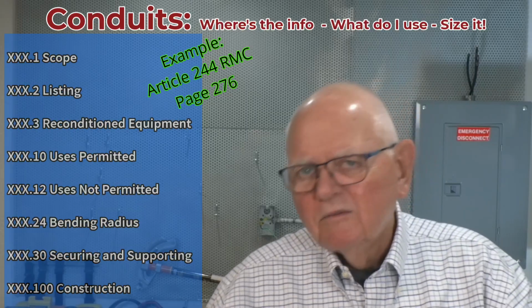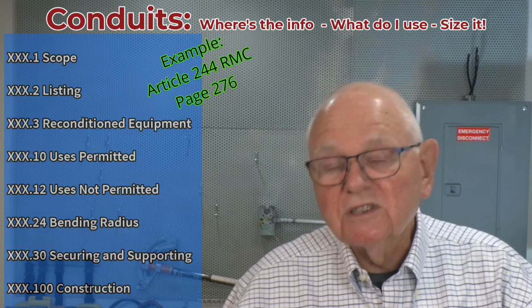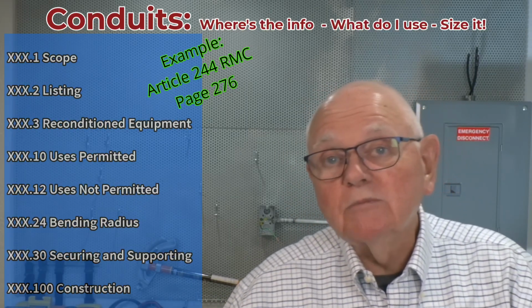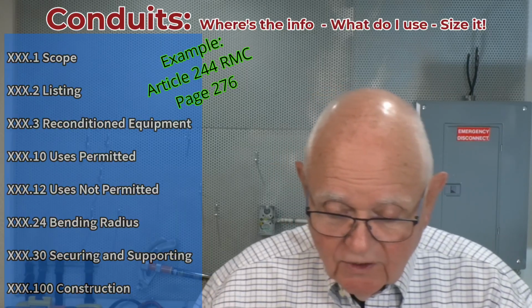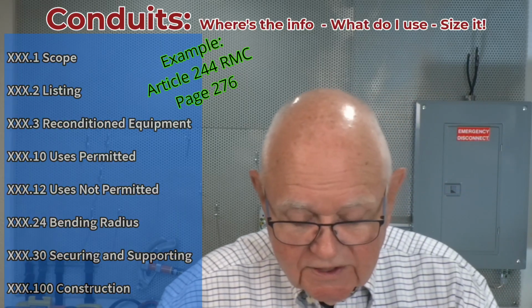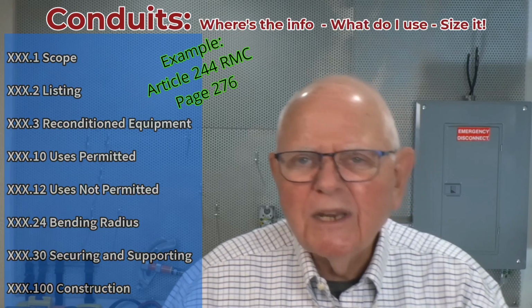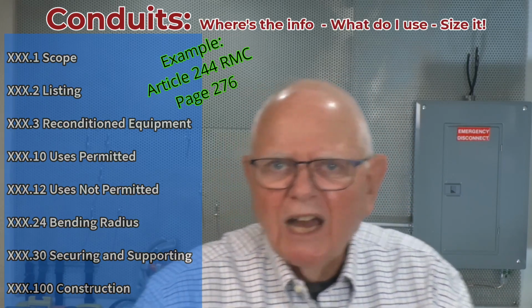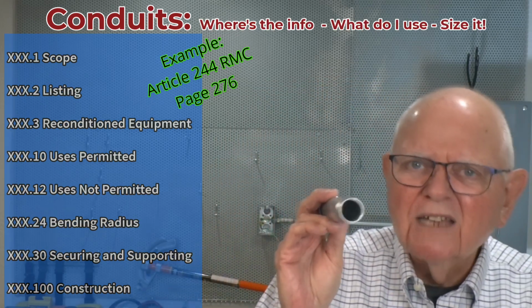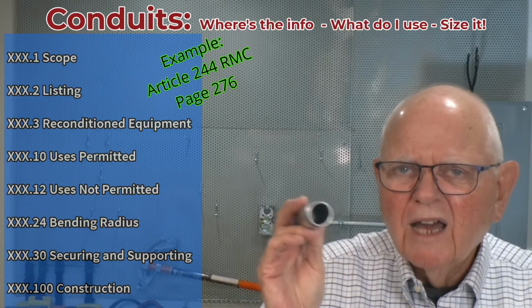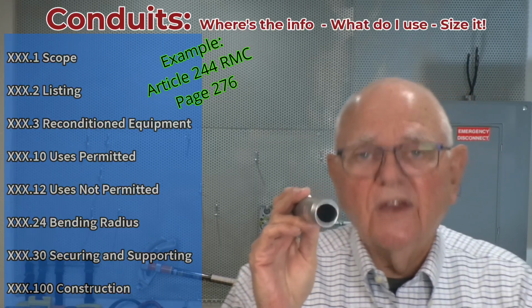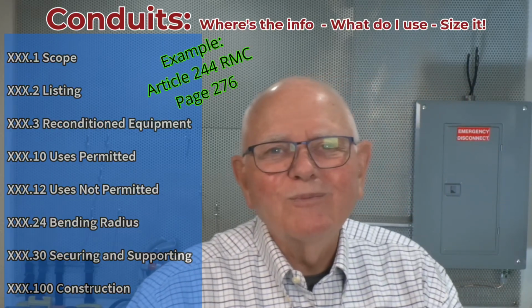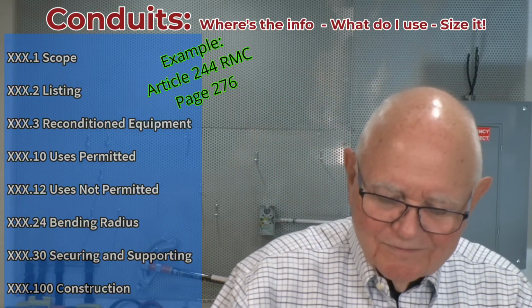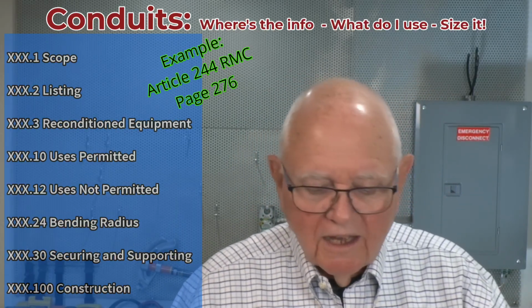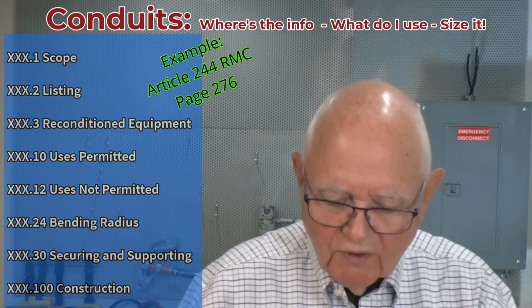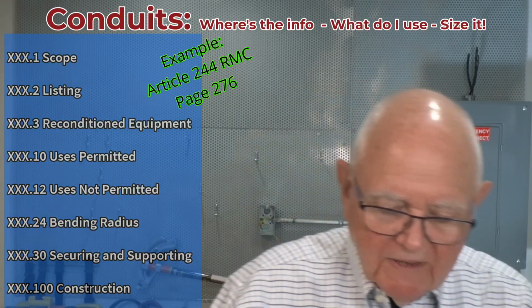344.20, my dot 20 section on my conduits is going to give me my minimum and maximum trade sizes for those conduits. The number of conductors is dot 22, and how many conductors can I put inside of this rigid conduit? And the answer is, it depends. Well, how do I know what it is? Well, go look in Chapter 9, Table 1. Okay, and we're going to head there in a little bit, and we'll be able to figure that out. It's going to be nice if they're all the same size. I'll just be able to use one informative annex.